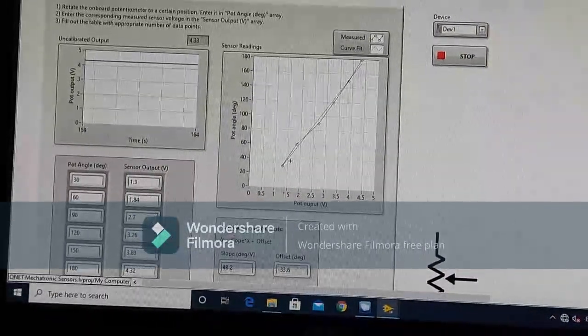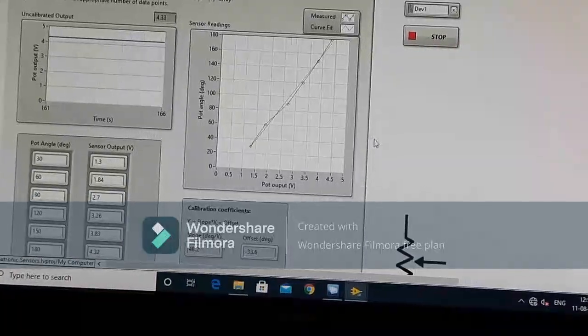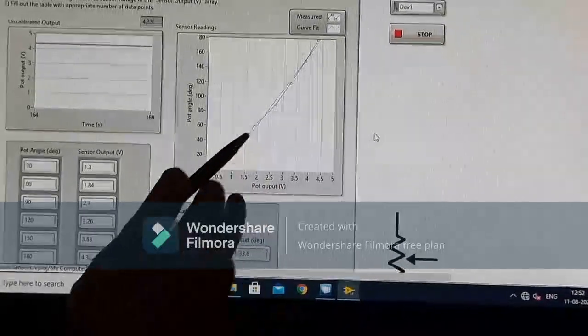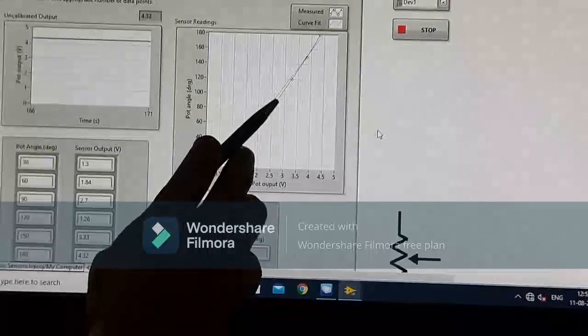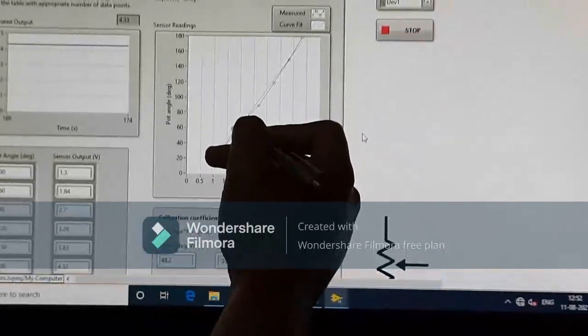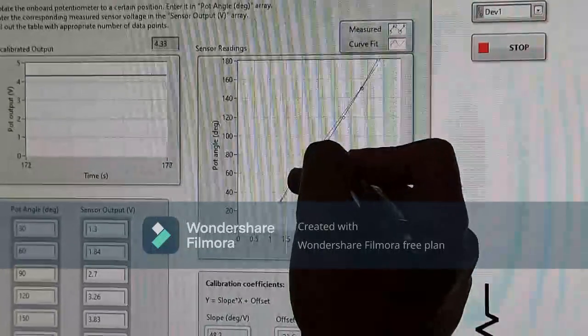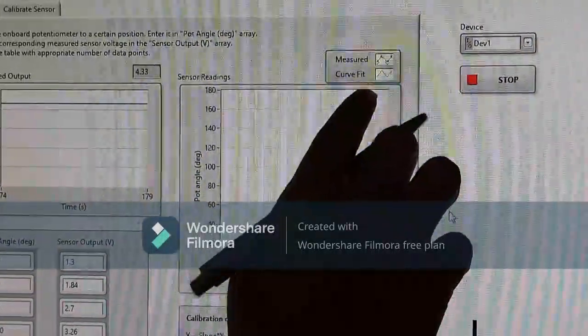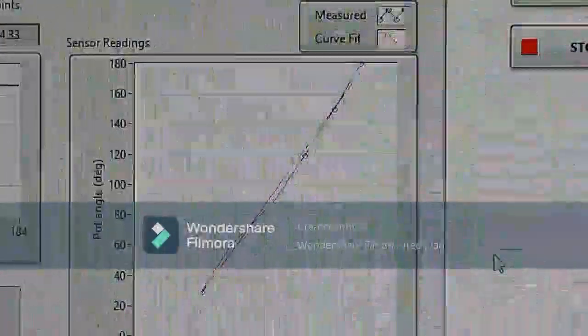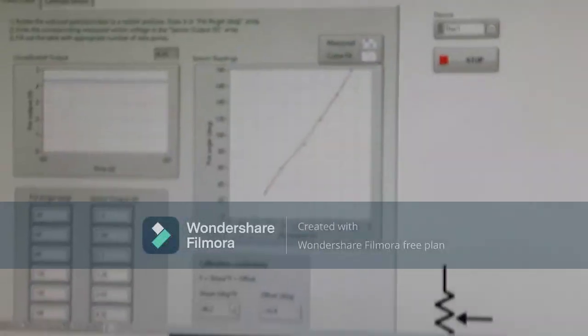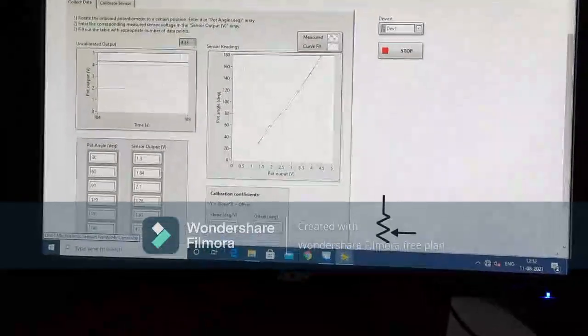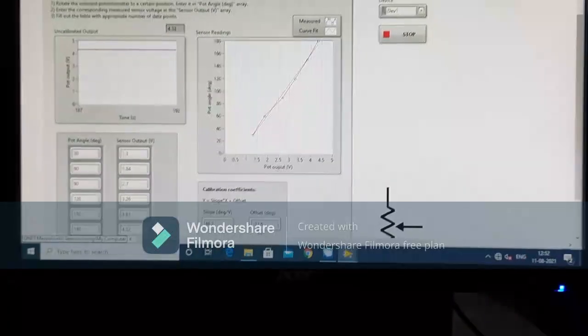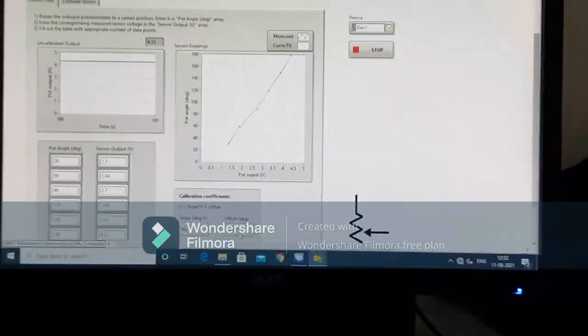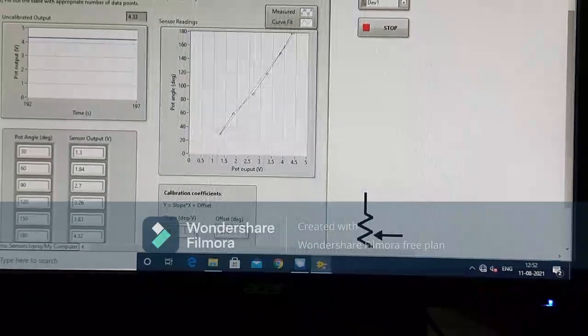If you look very carefully, the red line is almost straight. But if you look carefully at the blue line, you will find one point here, one point here, one point here, so I have some kind of deviation in this line. Again I have one point here, one point here. But the red line is the standard line, so it is almost straight, and it should be straight, fine, no problem. Below you can see I am getting the slope value, that is 48.2, and minus 33.6, that is the offset in degrees, fine. So this is the slope and the offset I am getting.